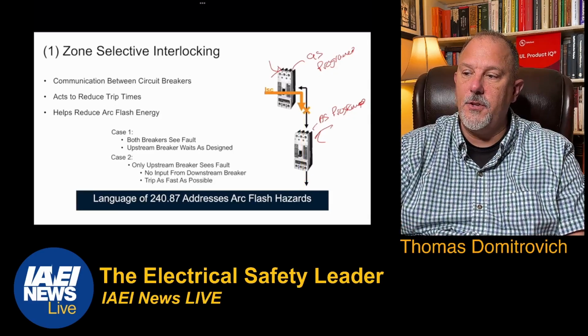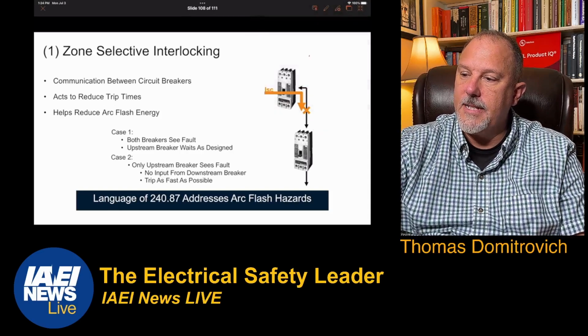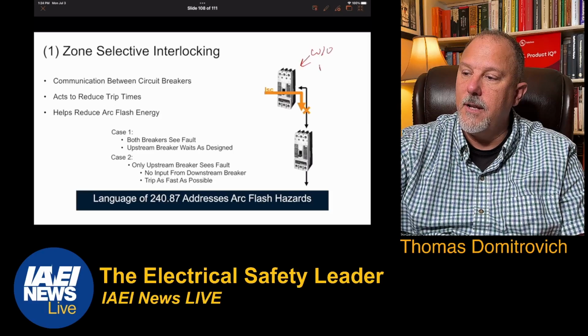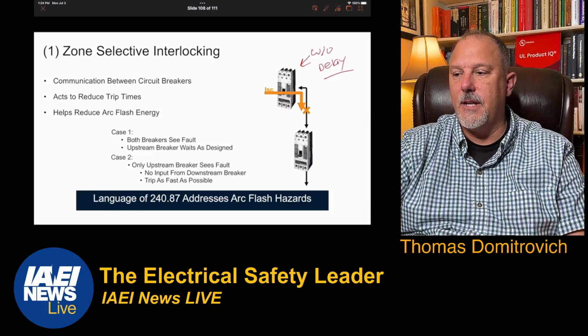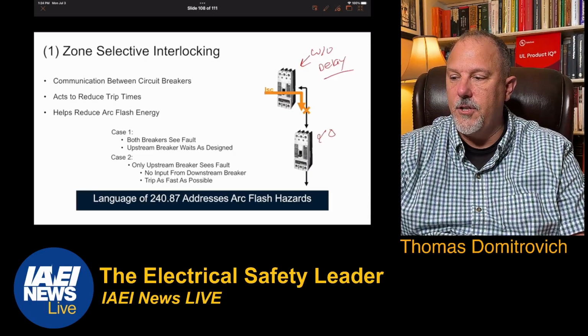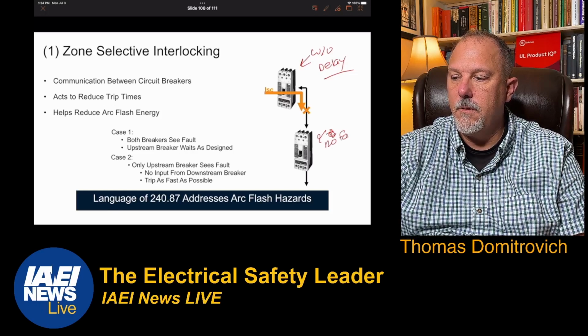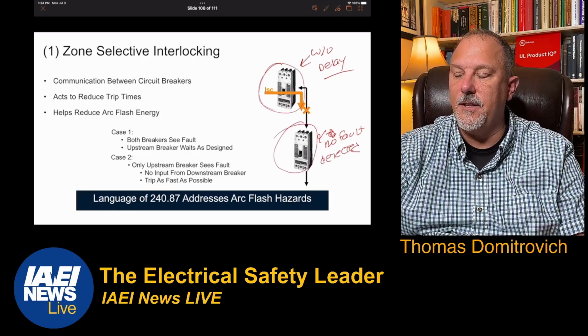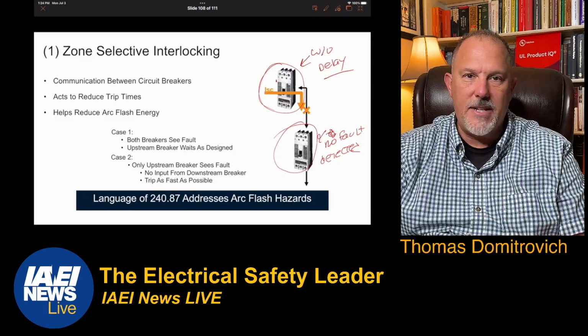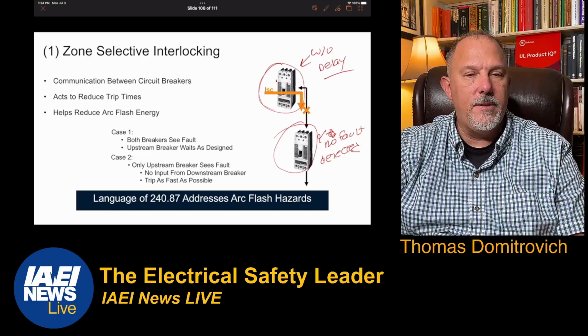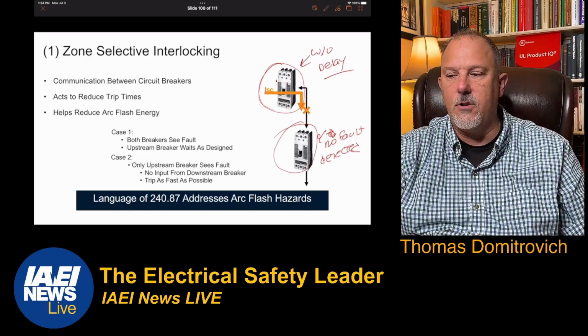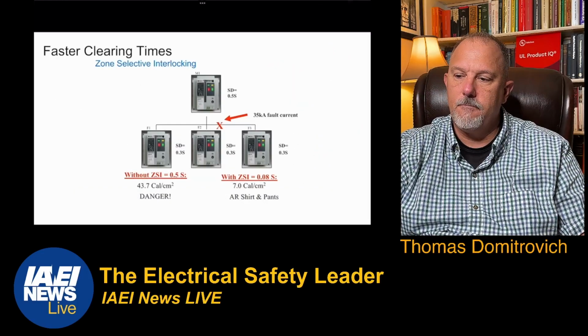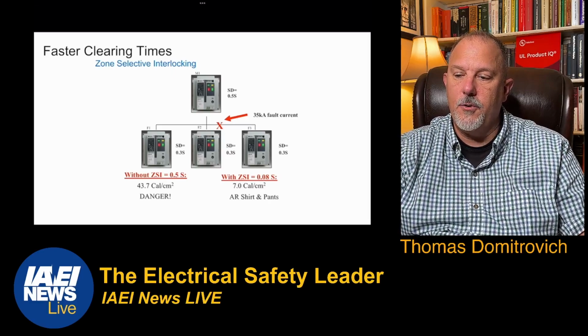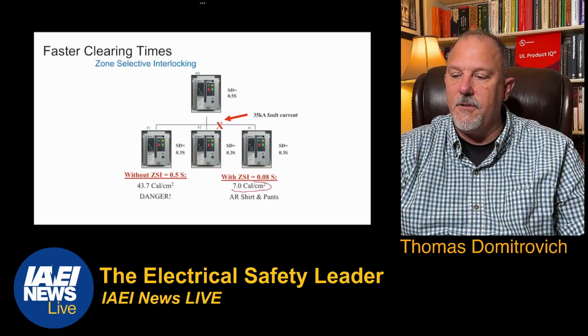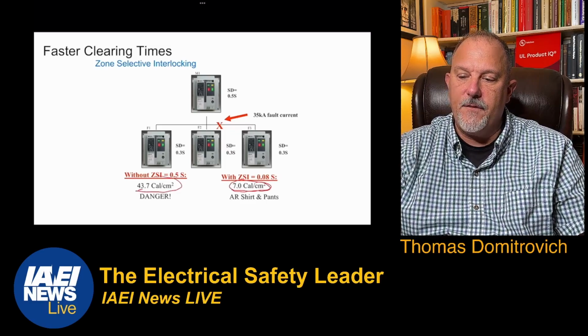If I have a fault in between the two, then this guy goes without delay. He goes without an intentional delay because the downstream sees no current, no fault detected. So this guy here does not see the fault. This guy does see the fault. This guy knows because they're talking to each other via basically a twisted pair that has a voltage signal. When the upstream device sees the fault, it looks at that twisted pair. If it doesn't see a signal from the downstream device, it trips without a delay. And this is the difference. For a fault in between here, you go down to 7 calories per centimeter squared. And if you don't have that, you're at 43.7.